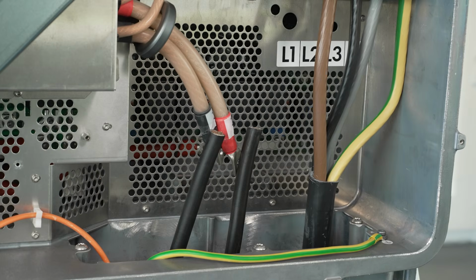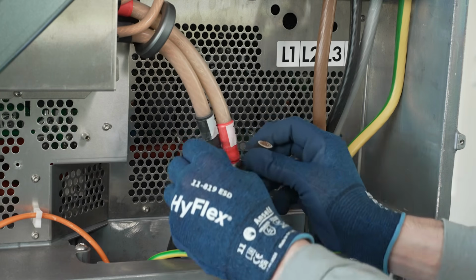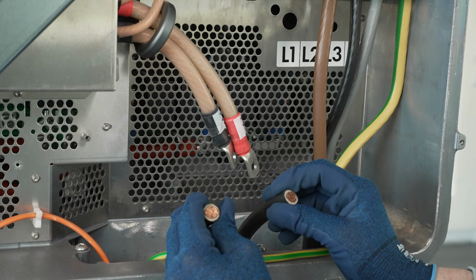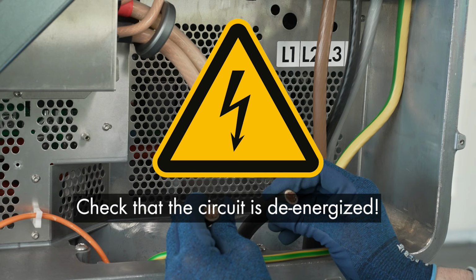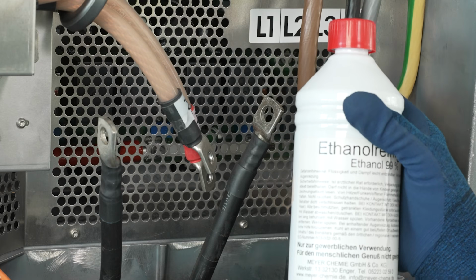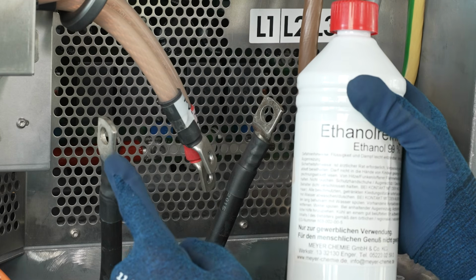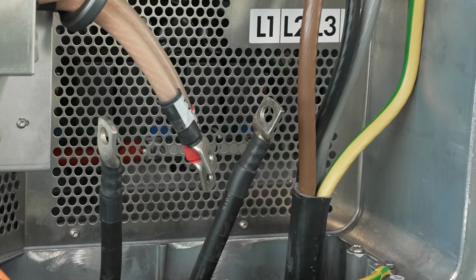Before connecting to the inverter, please ensure that all the requirements for the DC connection have been met. Only when all prerequisites are met do we begin with the connection. First, we make sure that there is no voltage on the DC cables. Then, we prepare the DC conductors. Next, we clean the contact surfaces of all cable lugs with a clean cloth and ethanol cleaner.